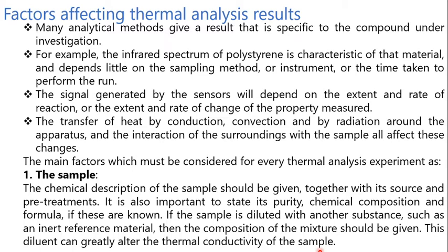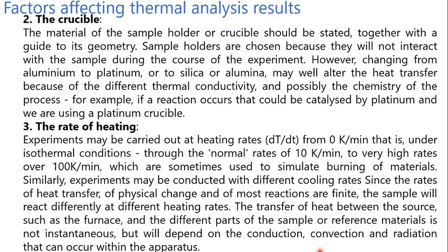The main factors which must be considered for every thermal experiment are as follows. The first one, the sample. The chemical description of the sample should be given, together with its source and pre-treatments. It is also important to state its purity, chemical composition and formula, if these are known. If the sample is diluted with another substance, such as an inert reference material, then the composition of the mixture should be given. This diluent can greatly alter the thermal conductivity of the sample.